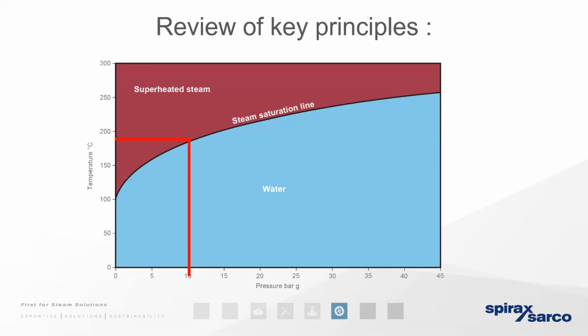But we know that we reduce the pressure of the steam at the process. We do that for a number of reasons. For one, it means that we're able to keep the steam as dry as possible. We're able to minimize the distribution losses. We're able to distribute it at a higher pressure. We're able to control the temperature of the steam by manipulating the pressure. So if we've reduced the pressure down to 2 bar gauge, 132 degrees, well, the condensate is also reduced down to 2 bar gauge, 132 degrees. Therefore, we know that whenever we get a fall in condensate pressure, we need a fall in temperature. And therefore, we know that we're going to get a release of energy that results in that flash steam that we've spoken about on so many occasions.